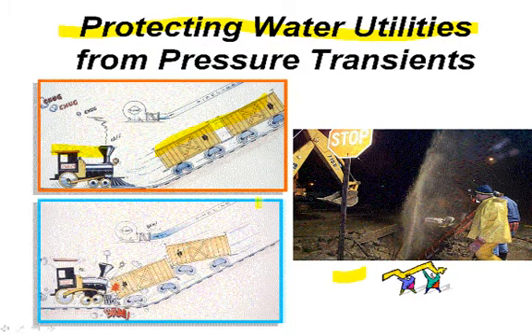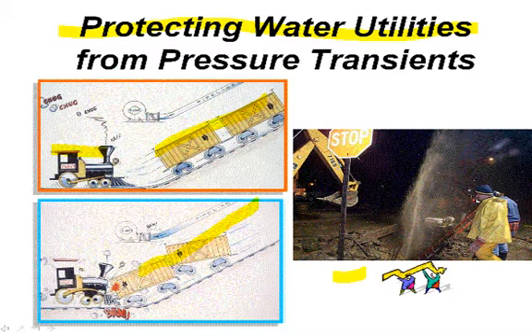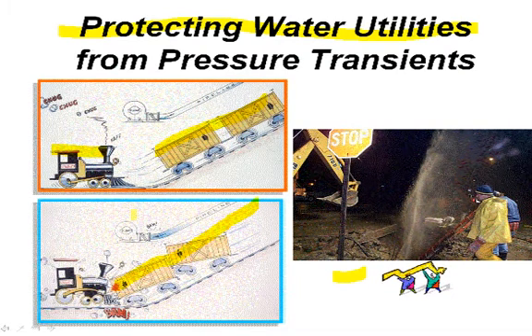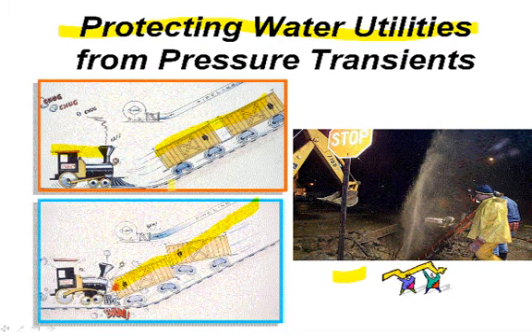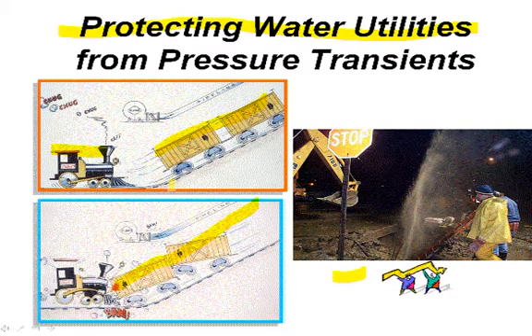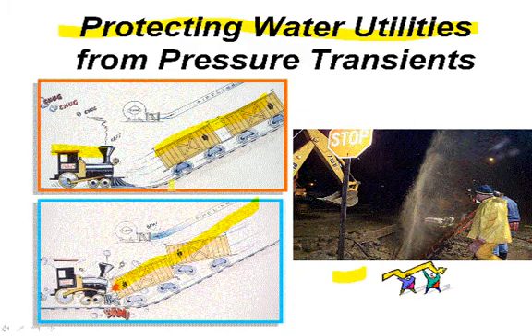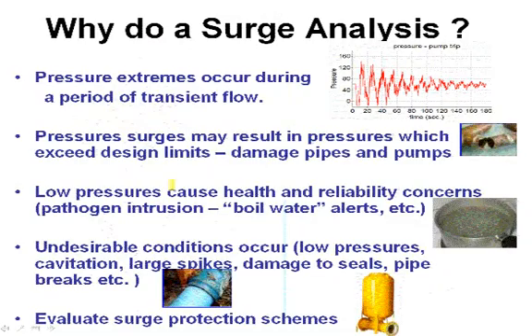Here's the train coming back and causing a big pressure spike at the pump. This is a serious problem that we have to be very careful to avoid. So why do we need to do a surge analysis for a water utility? The extremes always occur during transients.